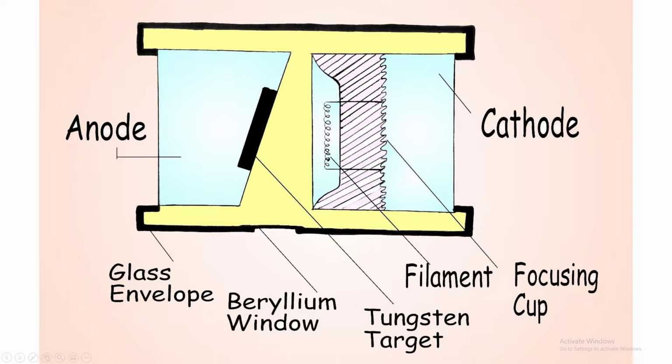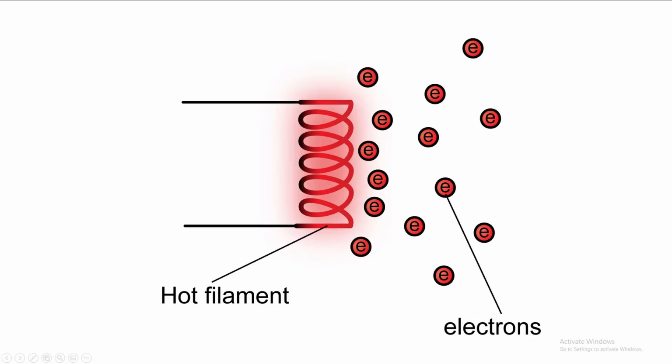How do X-rays work? X-rays are produced when electrons are created inside the X-ray tube, specifically in the cathode filament. The electrons are made through a reaction known as thermionic emission, where electrons are emitted in response to heat. This is done by an electrical current passing through the filament, making it hot. This dissociates the electrons from the filament and creates an electron cloud around the filament.